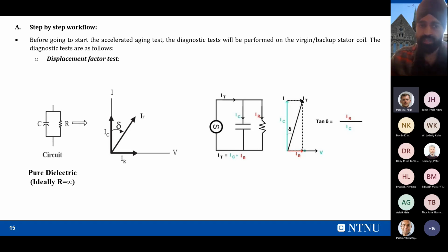In the ideal case, the capacitance has a resistance value that is near infinite. If the resistance is infinite, there will not be any leakage current or any type of current flowing through that insulation, because its property is to insulate, so it will not allow any kind of current to flow. If the resistance is huge, it will resist the flow of current. So for an ideal case, this R is infinite, but in actual scenarios, this R is not infinite.